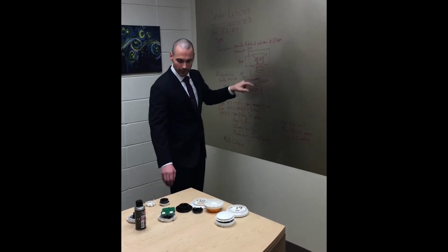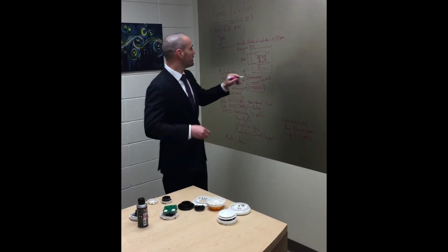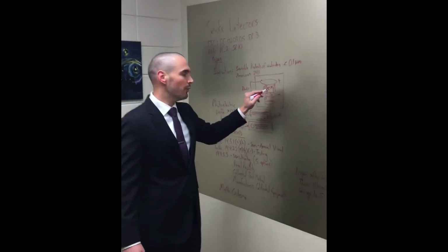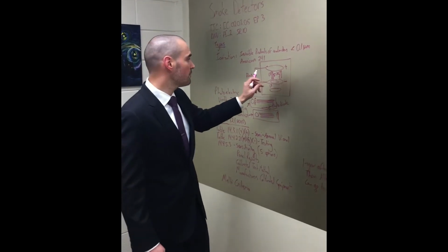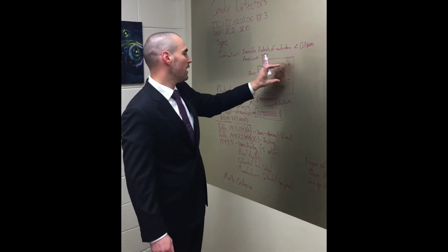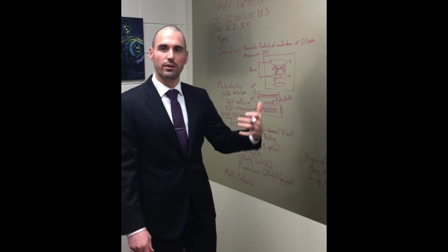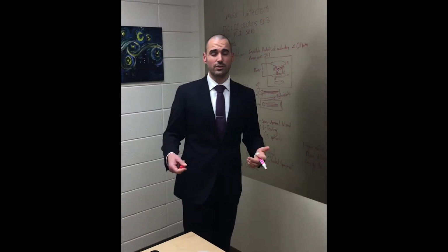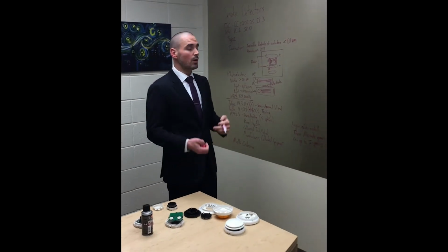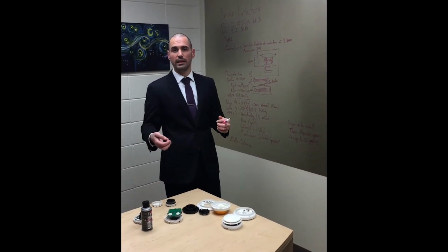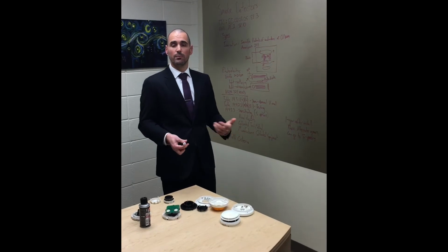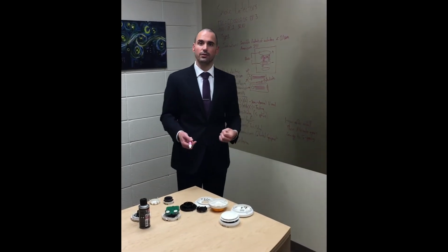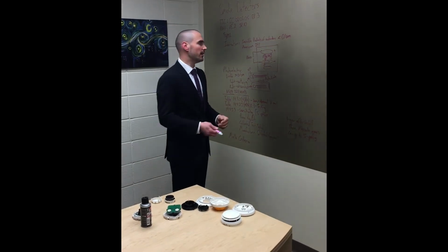When smoke enters in here, it actually disrupts this ion flow. When that ion flow is disrupted between these two electrical charges, that is what actually triggers the ionization detectors into alarm. So you probably don't have ionization detectors in your hospitals. Most common place that you'll see them is actually the stuff that you can buy from the store and use at your house. Ionization detectors are the most common type of detectors used for the battery powered.